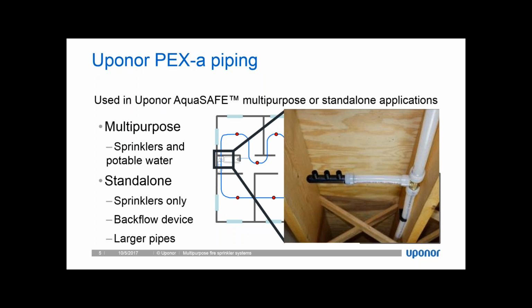Bigger pipes mean more materials and sometimes harder installation, and that's just one of the reasons why they're not as sustainable a choice as a multi-purpose system. Multi-purpose systems primarily utilize very small pipes. Because of the loop configuration, we're probably going to deal with 3/4 inch. Most of the sprinkler systems that Uponor designs are 3/4 inch, and some of them end up being 1 inch, but none of them get any larger than that. So it's a 3/4 inch or a 1 inch system all the time, and that's going to make estimating those systems a lot easier too.